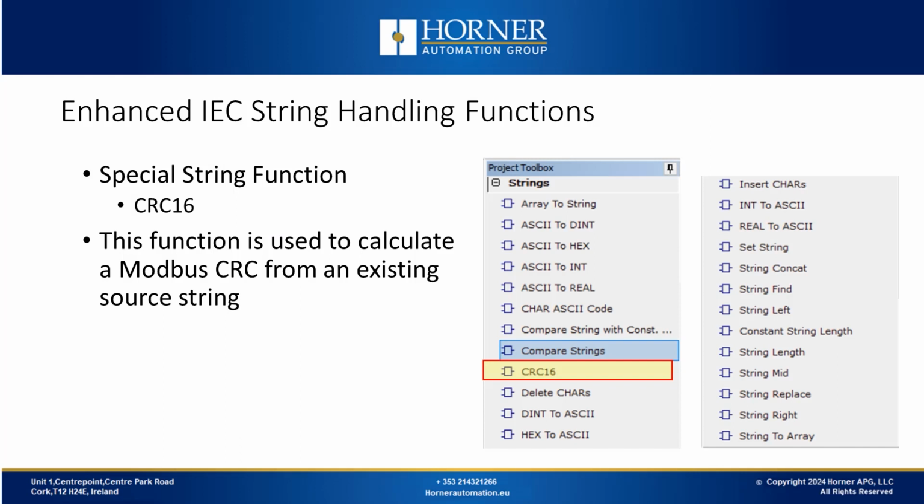Finally, we will take a quick look at a CRC calculation function, which is a built-in function in Enhanced IEC. We can use this to calculate the Modbus CRC from a source string. This could be used if you were building your own string and talking to a device that uses a non-standard version of Modbus, and you need to calculate a CRC.